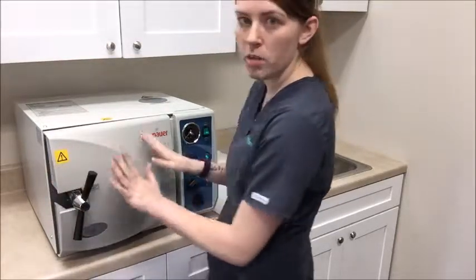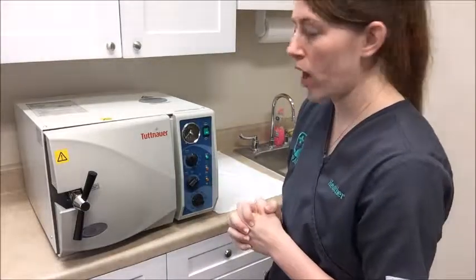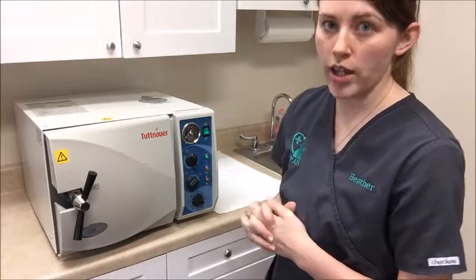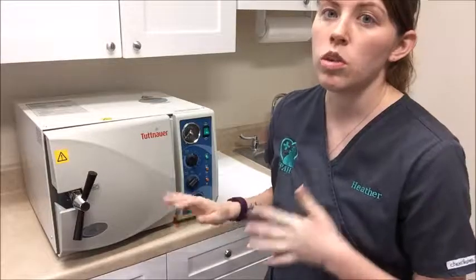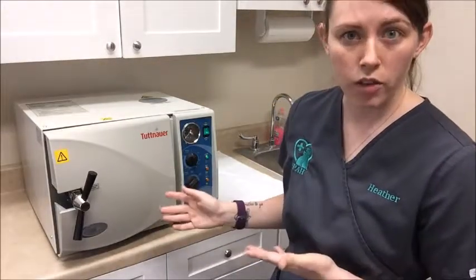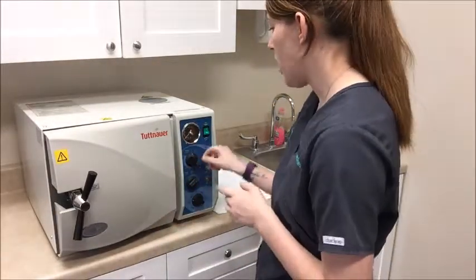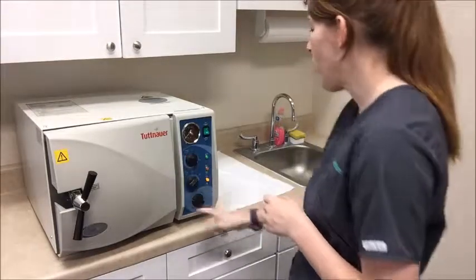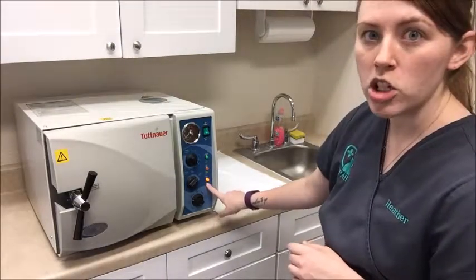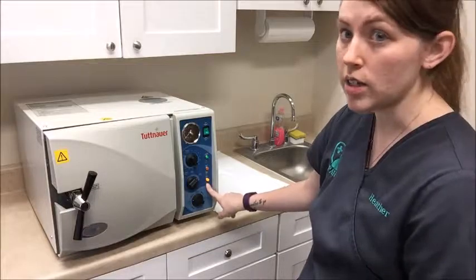Alright, so that's as far as I'm going to open it right now according to manufacturer instructions, and I'm going to set a drying cycle. According to the manual, the drying cycle should be set for 30 minutes as well. So I'm just going to set my timer for 30 minutes, and then my dry light is going to come on the machine to indicate that the drying cycle is in place.